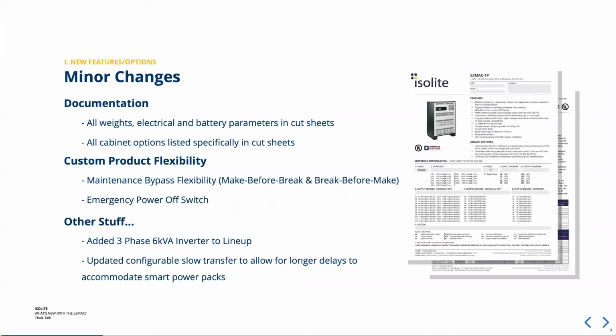The other thing is a firmware update we've made under the hood. If you've seen my Chalk Talks on the E3MAC, you've heard me talk about the impact of smart power packs with UL 924 ratings. They need to see an absence of power so they can go into override mode. We've always had the flexibility to change the transfer time on the E3MAC — by default it's a quick 2 millisecond transfer, and we've allowed it to go up to 1 second. We've now changed the firmware to allow extending that further to 2 seconds. That brings parity across the line, since there are power packs out there that state they need longer than 1 second gaps in power to operate properly. This now allows our products to be compatible and work natively with those power packs, so you never have to worry about getting caught out by that.